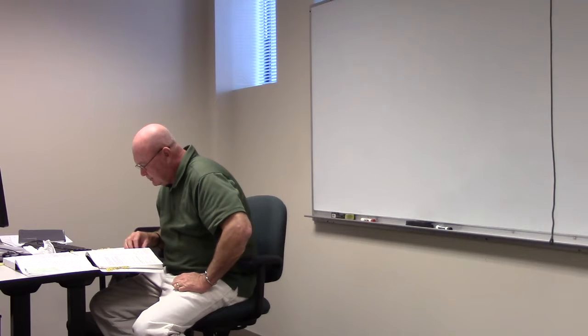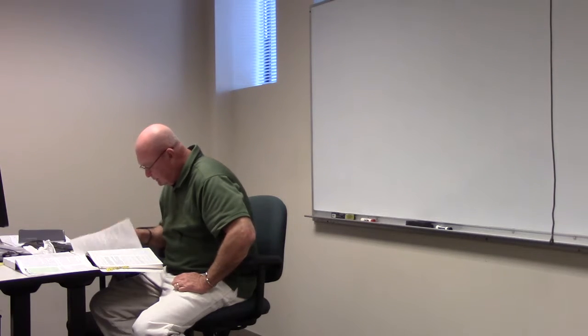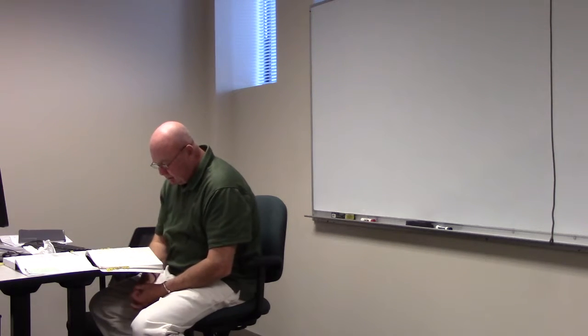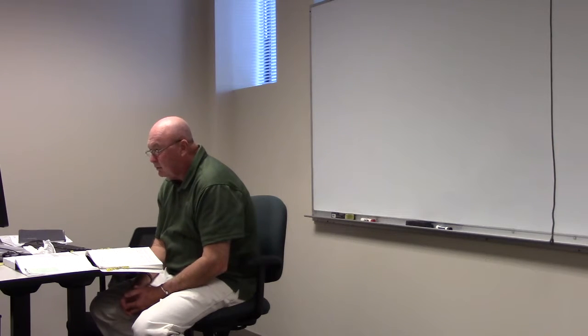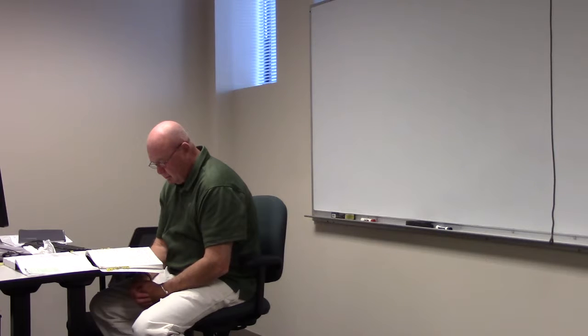220.18B talks about inductive and LED lighting loads. You can see what it says there about that. 220.43B is one we haven't covered yet. And B talks about track lighting. Track lighting, you probably have that in a jewelry store. You'd have a bunch of it, wouldn't you? Yeah. So it says for track lighting in other than dwellings, an additional load of 150 volt-amps shall be included for every 2 foot of track.